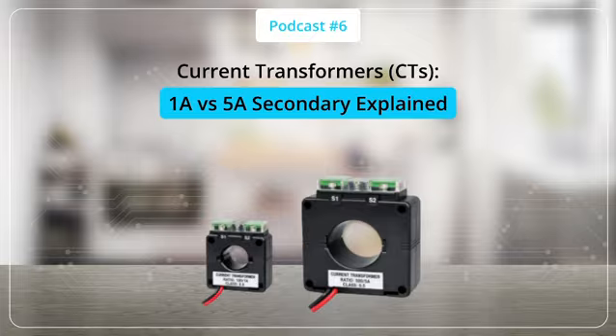A 5A CT, in contrast, has higher power loss and higher cable losses, but can handle a greater burden, making it suitable for shorter distances and heavy-duty applications. In terms of accuracy over long distances, 1A performs better, while 5A may show slightly reduced accuracy. Typically, 1A CTs are used in modern digital protection systems, whereas 5A CTs are common in traditional relay systems.